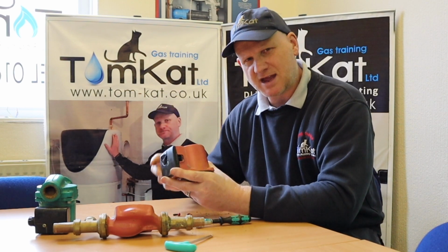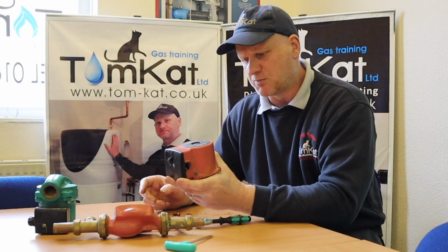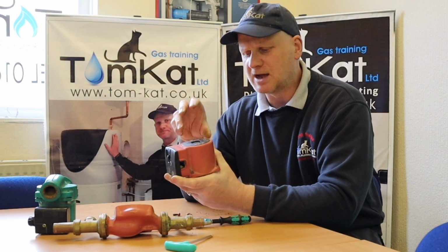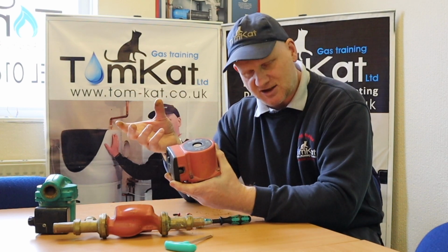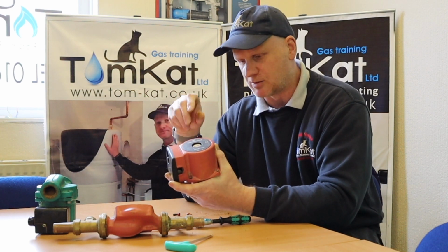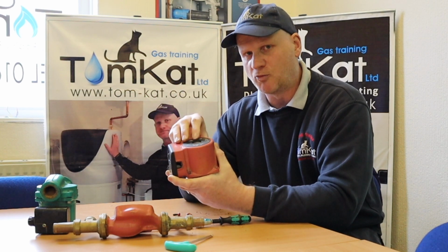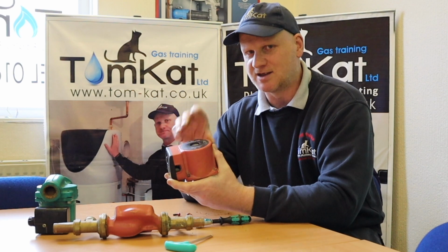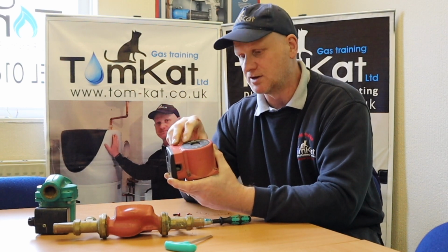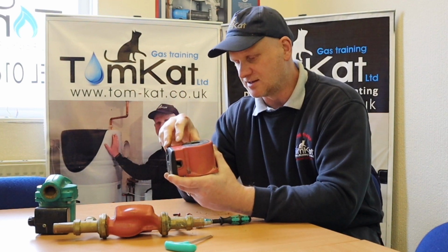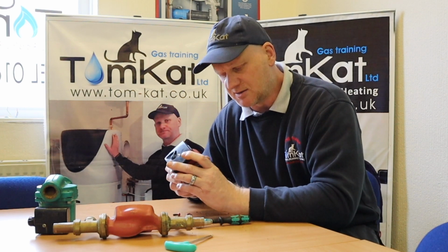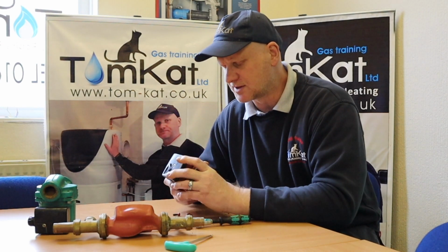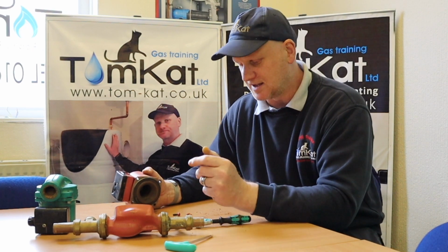So that's one of the major things what goes wrong with pumps, is they get full of air and they cavitate and they create this heat and it causes problems. So if you can hear your pump running, there's every chance there's air in there because you shouldn't hear it running. It could be running too fast for the heating system. So that's one of the major problems with pumps. So we've started to see what's inside these pumps, so let's have a closer look at them.